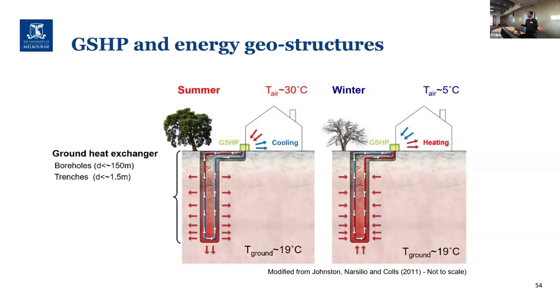The ground is at a very stable temperature throughout the year. The upper 100 meters of the earth is at around 18 to 19 degrees. In the case of Melbourne, it is typically the mean temperature throughout the year of the particular location. And because the water that we inject is at 30 degrees, say, and the ground is at 20, the ground acts as a sink of heat. We're rejecting heat to the ground. Now that fluid comes back to the surface, to the green box over there, maybe 3-5 degrees lower in temperature. That differential in temperature is used by the heat pump to then provide either cooling to the building on top, or heating if we do a reverse cycle.